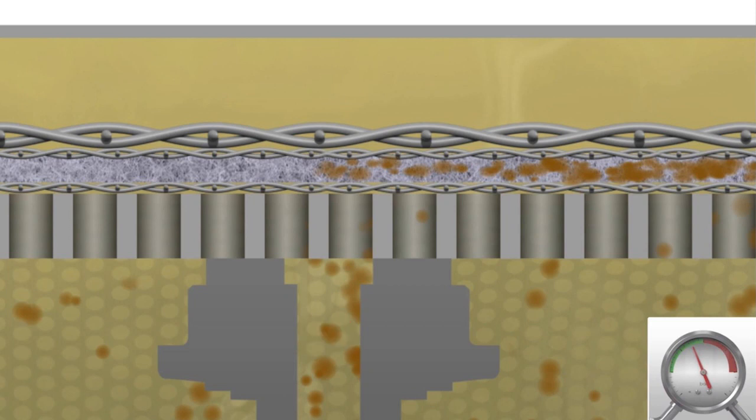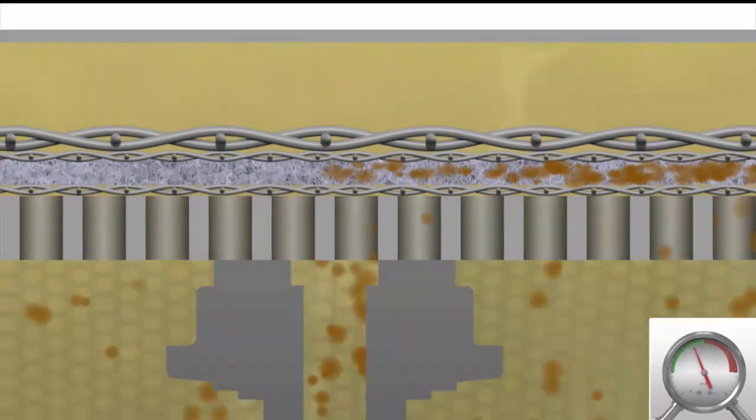The backwashing is carried out with small amounts of filtrate, which flows from the filtrate chamber P2 into the reject chamber P3. The pressure difference between P1 and P2 is much smaller than the pressure difference between P2 and P3, which causes backwashing at much higher velocity and intensity than during filtration in the opposite side.